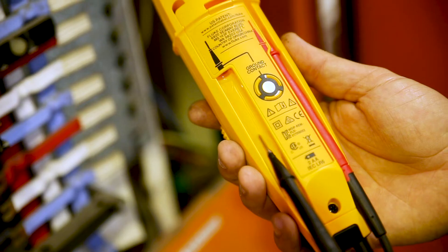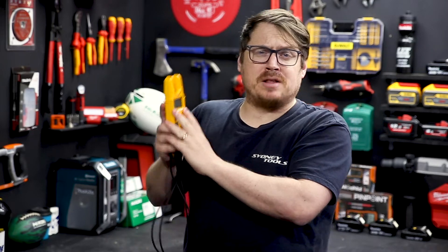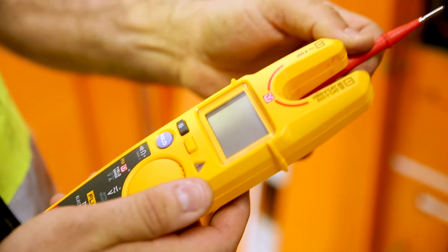When using the FieldSense, make sure the black test lead is docked in the rear and that your finger is pressed against the ground contact as well. Other features include the dual display, so it shows both voltage and current simultaneously. It also auto-selects when measuring voltage, AC or DC. Super nice, well thought out design.